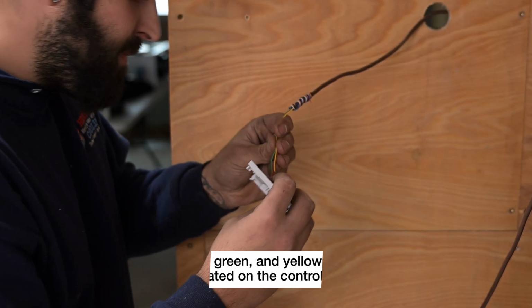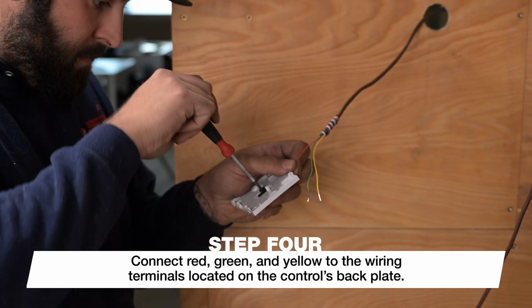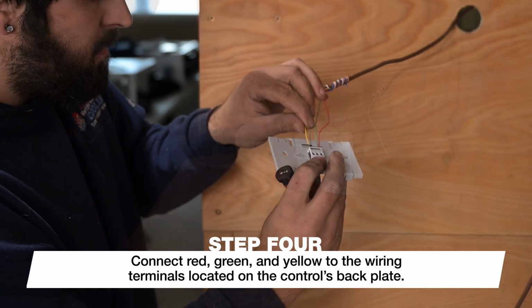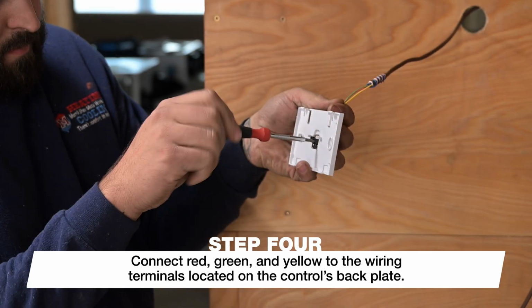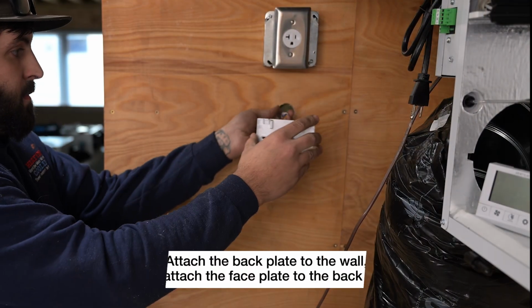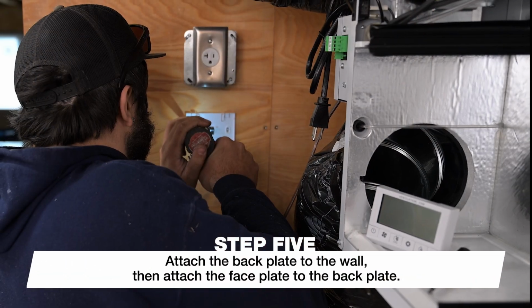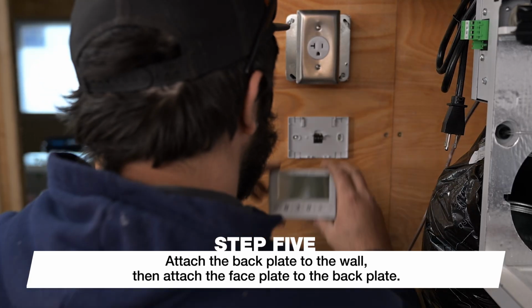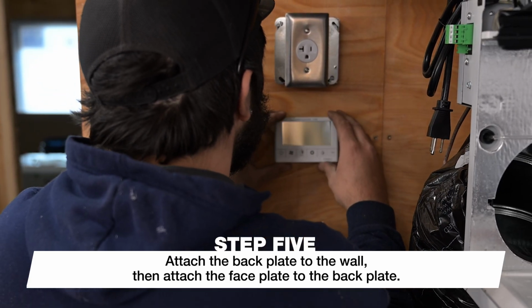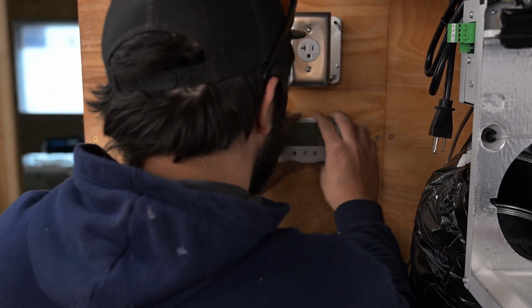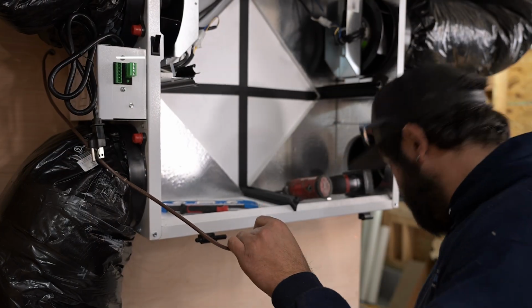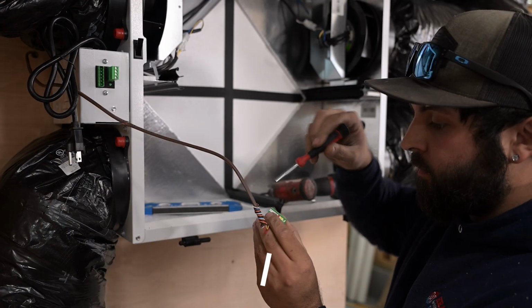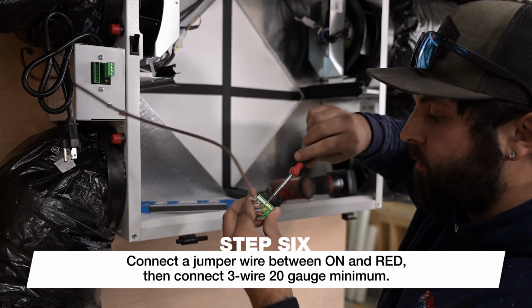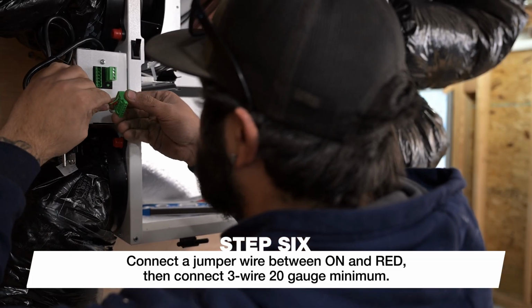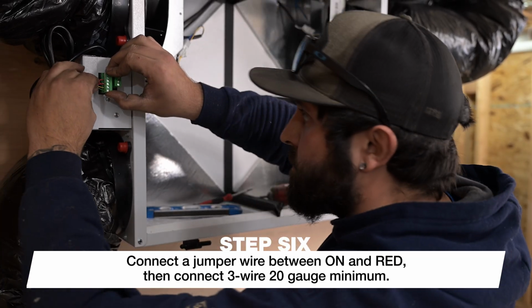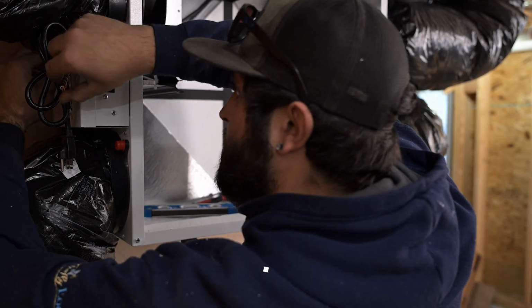Using 3-wire, 20-gauge minimum, connect red, green, and yellow to the wiring terminals located on the control's backplate. Attach the backplate to the wall, then attach the faceplate to the backplate, being careful of the alignment to avoid damaging the contact pins. On the terminal block located on the ERV, connect a jumper wire between on and red, and connect the 3-wire 20-gauge minimum, red, yellow, and green. Now you can power on and test the unit.